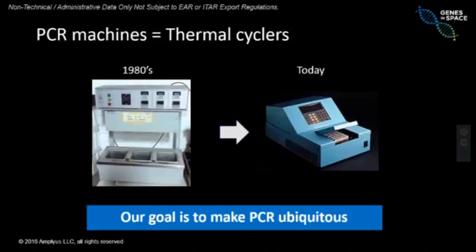PCR machines help us do PCR. All your reagents — your DNA, primers, enzyme, and the nucleotide letters A, T, C, and G — go inside a plastic tube. Abstractly, we are heating and cooling that tube through three temperature steps: 94, 72, and 50 to 60 degrees Celsius. If you could move that tube between these temperatures, you essentially can do PCR. In the very early days, people used three water baths at these different temperatures for denaturation, annealing, and extension — that was a kind of manual PCR machine.